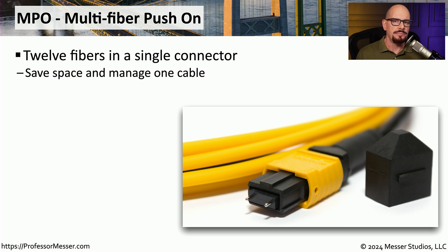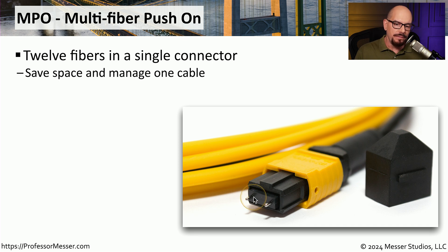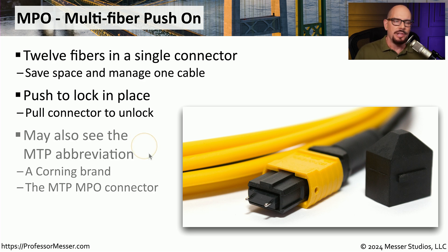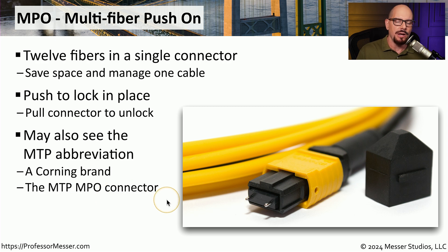One of the challenges with the connector types we've seen so far is that those fiber connections take up a lot of real estate. It would be a lot more efficient if we could put more fiber into a smaller connection. There is a connector type for that called the MPO, which is multi-fiber push on. Inside the MPO are 12 individual fibers contained in that single cable connection. This also has a lock in place very similar to the SC connector, where you push it in and pull it out slightly to unlock it from the interface. You might also see this connector referred to as an MTP — a name provided by Corning, who refer to it as an MTP MPO connector.